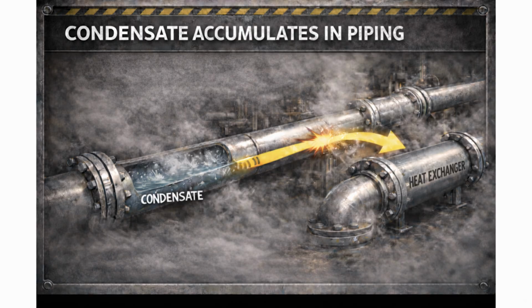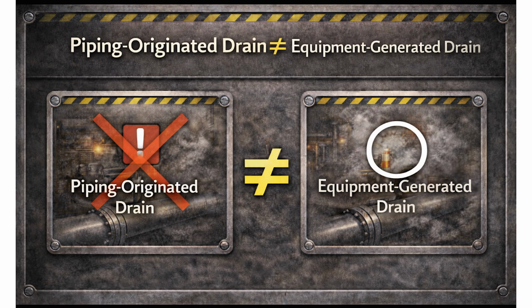When this happens, condensate accumulates inside the piping. At some point, the accumulated water suddenly begins to move. It travels together with the steam. Then it flows downstream into the heat exchanger. One point here is very important. That condensate was not generated inside the heat exchanger. The size of an orifice is designed based on the condensate generated inside the heat exchanger. It is not designed to handle irregular water suddenly coming from upstream piping. This is not a defect of the orifice. The design assumption has already been broken.